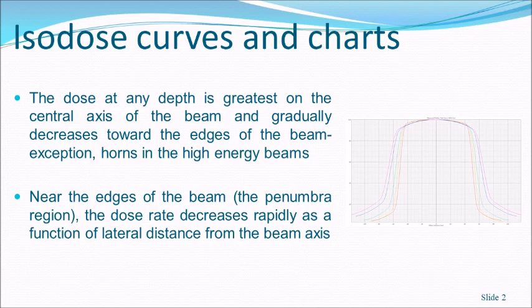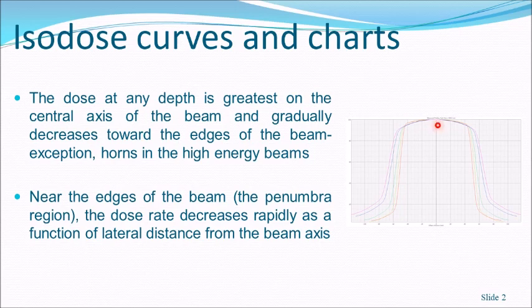Isodose curves or charts are obtained by measurement in a water phantom. Usually the dose at depth is greatest on the central axis of the beam. The dose is maximum at the central axis and gradually decreases as you go off axis, except for the case of horns in high energy photon beams due to the flattening filter. The dose at the central axis is higher than at the off-axis region and decreases as you move away.